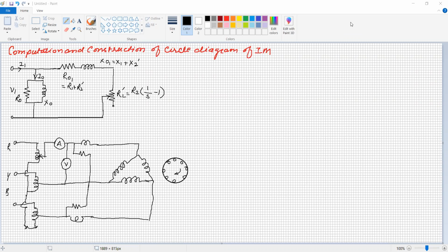It will give the facility to examine the vibration, temperature rise of motor or sparking somewhere. But if the capacity of motor is very high, it is quite difficult to test the three-phase induction motor in the lab. So the second method is the indirect method. In this indirect method, only no load data and block rotor test data is useful for calculating the different losses in the motor as well as efficiency and its speed for the different load condition.